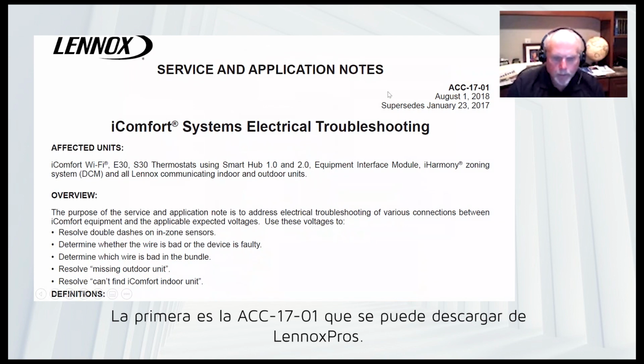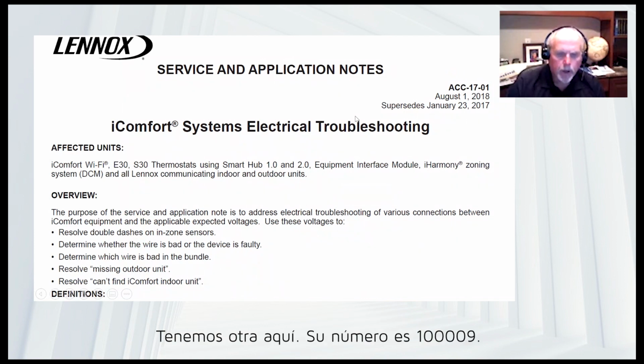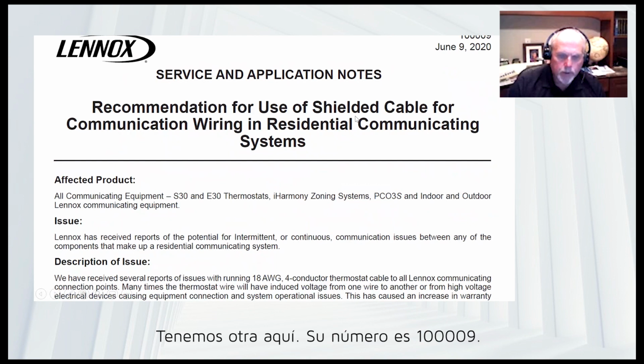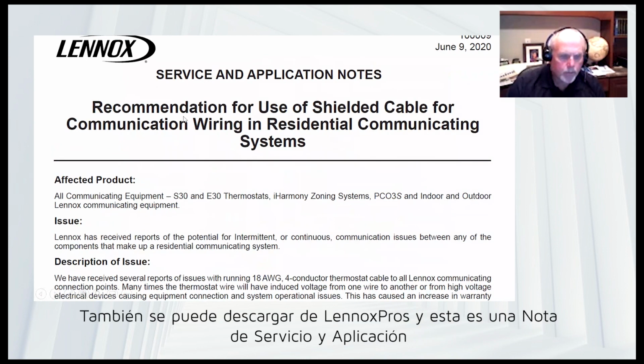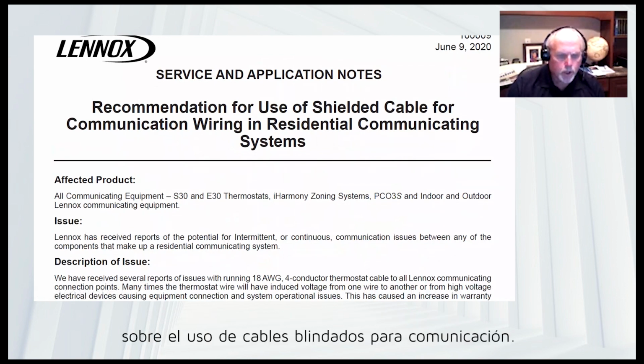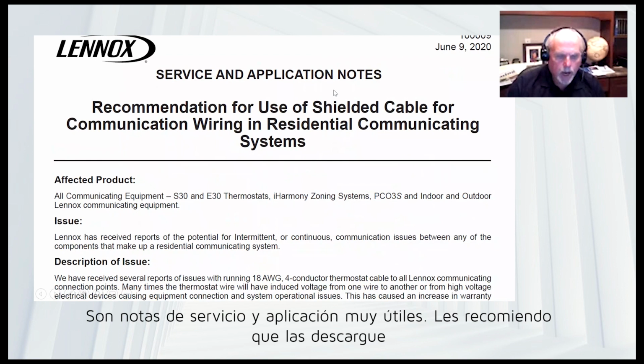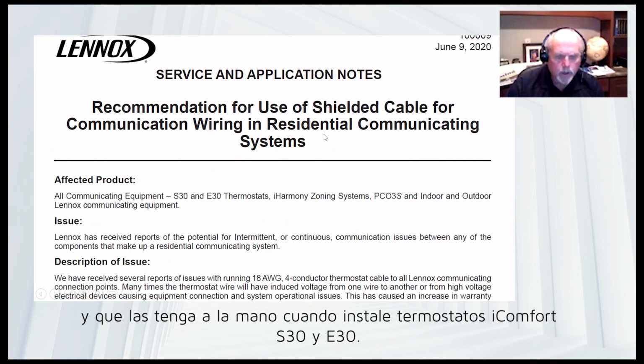That could be downloaded from LennoxPros. And we have another one here. The number on it is 100009. It also can be downloaded from LennoxPros, and this is a service and application note on the recommendation for using shielded cable for the communication wiring. Okay, it's a very good service and application note. I would highly recommend you download those and have those with you when installing or troubleshooting S30 or E30 thermostats.